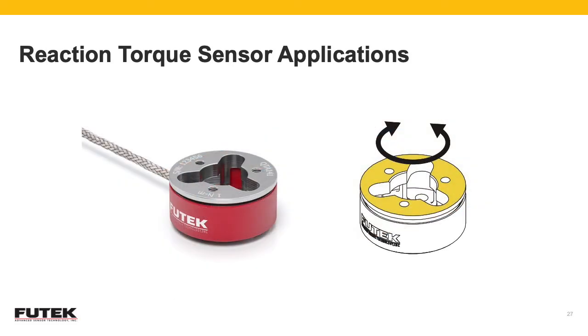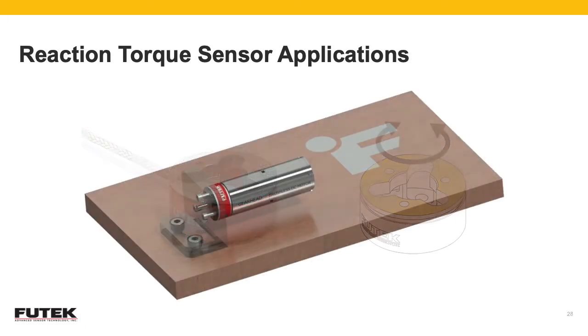Here we can get a better look at the product and how there is a cavity to allow for a shaft to enter the middle of the sensor. The sensor is sandwiched between the flange and the gearhead, and as it engages with the mechanism on the right, we are able to take the measurement as torque increases.